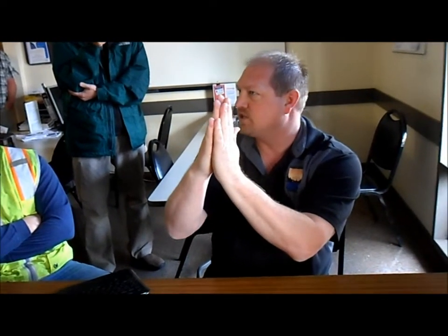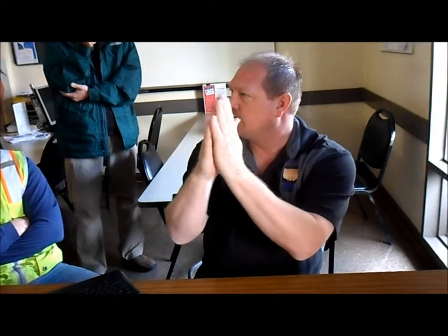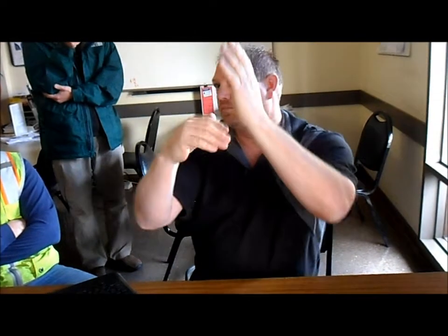Easier to operate with pressures because of the pressure on the valve. With 8 and 10-inch, since the seat's going up and down, you don't have that much issue with the pressure. It's pretty easy to move them. But when you get over 10, 12-inch, when that water pressure is high on one side and there's no water on the other, it's pretty hard to make that turn. With the butterfly valve, when it slightly turns, it releases that pressure instead of trying to force it up again. So it does work pretty good.